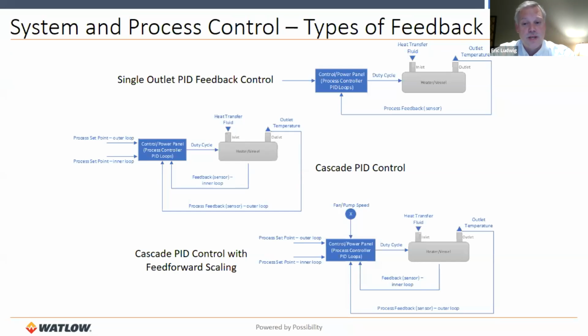There's a latency sometimes of your heating system to react to that. If we're just using feedback control, you have to wait for that fluid to take effect on the sensors in the system. But if we have a sensor on that fan and pump speed that we can put into the control system, then we can anticipate that additional heat load need and start to react to that quicker. So we call that a feed-forward scaling system, and that's typically used, like we said, in those modes that we would expect a transient response to occur.